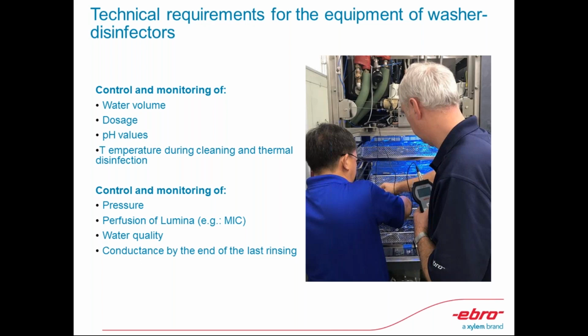You can see the picture here that Ivan actually used a conductivity meter with a probe, and that made us decide to open up the washer disinfector just to introduce the cable probe from outside to inside, positioning the sensor near the drain of the washer disinfector. I must remind you that this was resolved and we have a solution with a wireless conductivity logger.